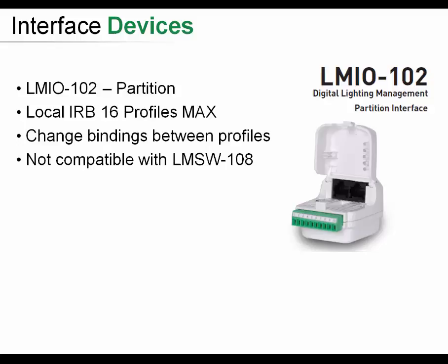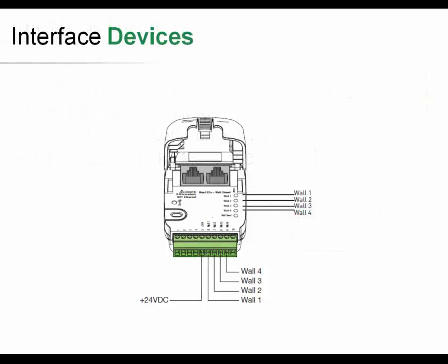The LMSW-108 is not compatible with the LMIO-102 or any of the WattStopper partitioning devices. So right away, if you see that you've got an LMSW-108 on the IRB, it is not going to work.